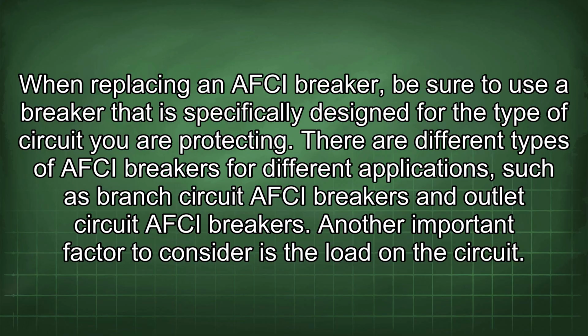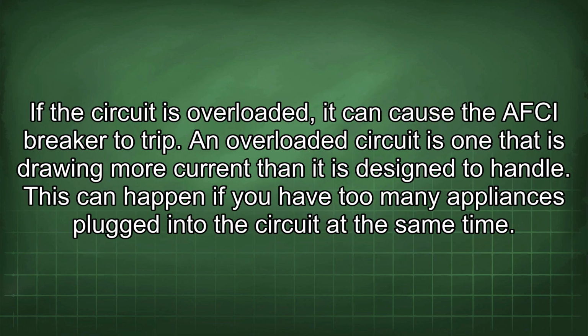There are different types of AFCI breakers for different applications, such as branch circuit AFCI breakers and outlet circuit AFCI breakers. Another important factor to consider is the load on the circuit. If the circuit is overloaded, it can cause the AFCI breaker to trip. An overloaded circuit is one that is drawing more current than it is designed to handle. This can happen if you have too many appliances plugged into the circuit at the same time.